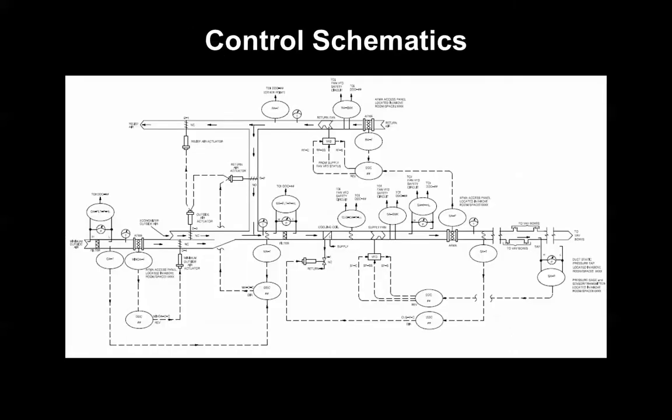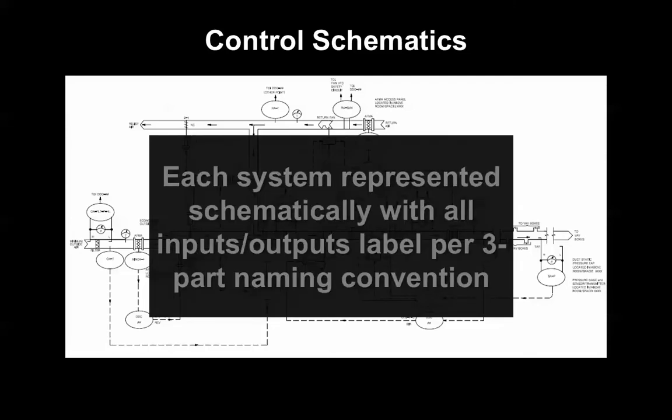We also looked at some control schematics and saw how condensed these were with information. So with something like a system diagram backdrop, you have an overall look at your system, and you have all of the different points, the inputs, the outputs, tied to the controller, as well as what goes to a safety switch, what type of manual gauges you have to look at your system, and what the point naming convention is. So each system should have this schematic representation with some of those standards about input, output, and how we name our DDC points.